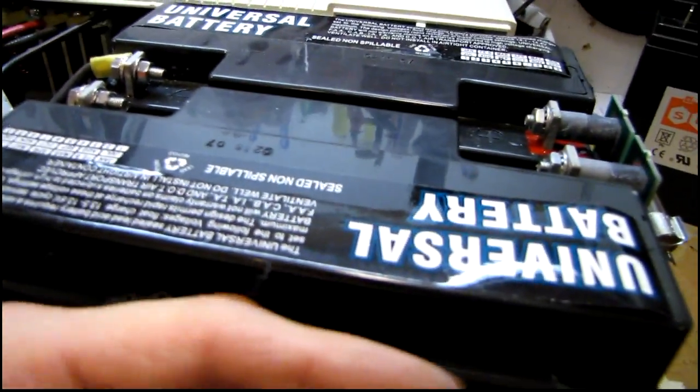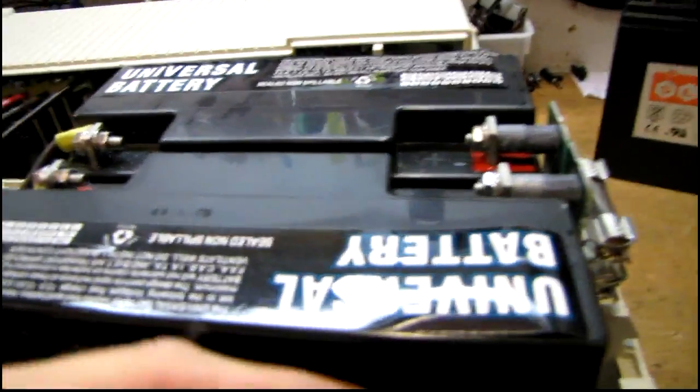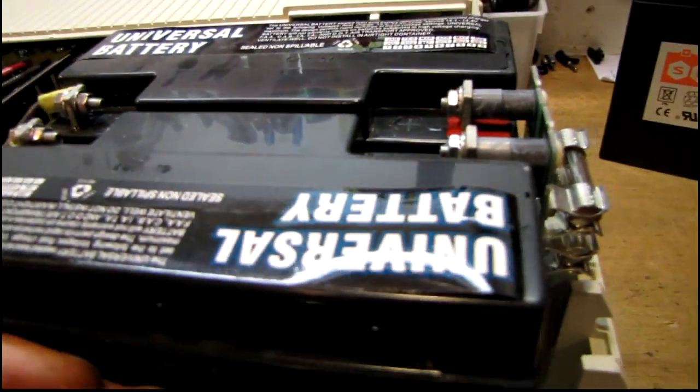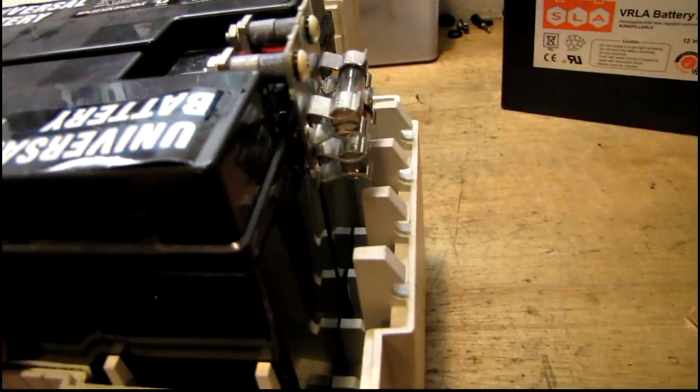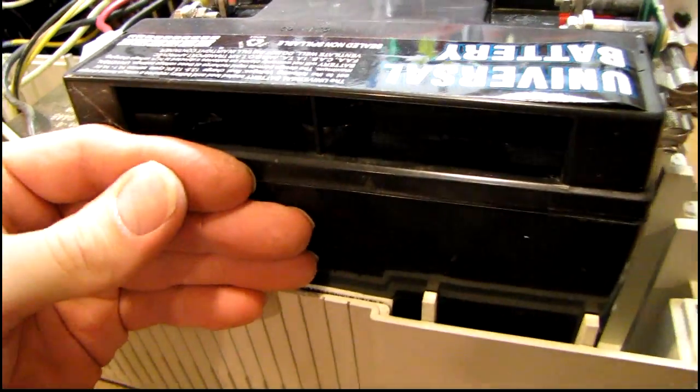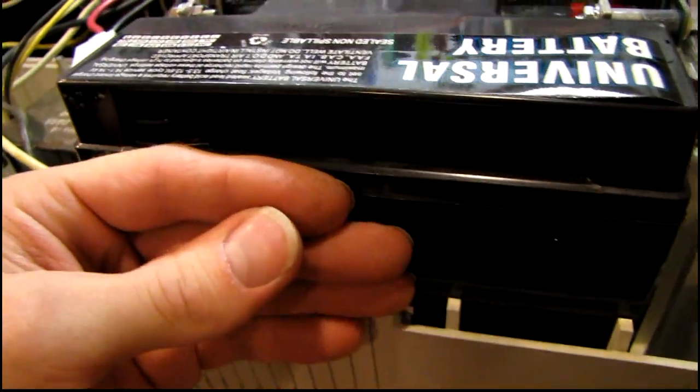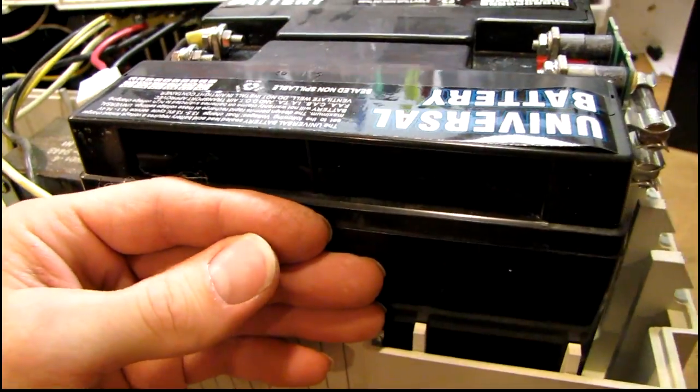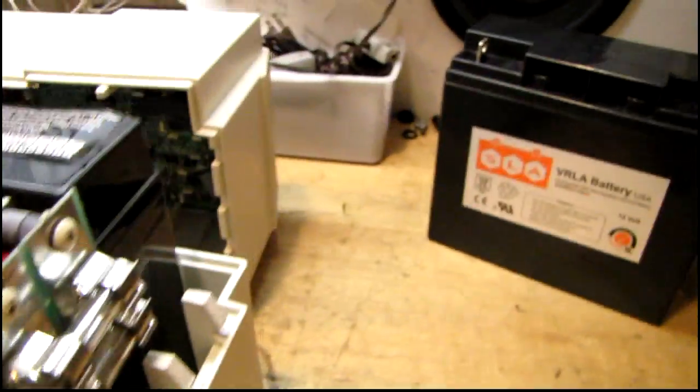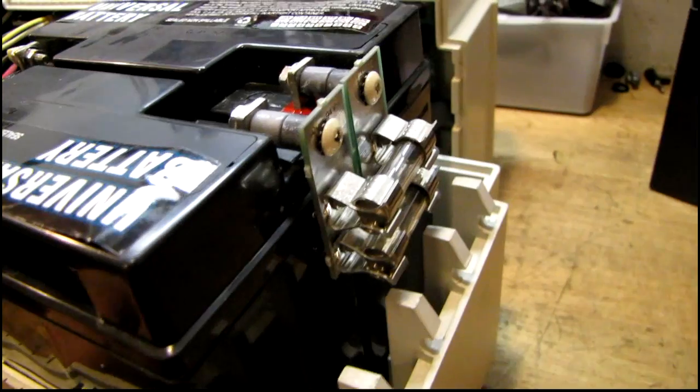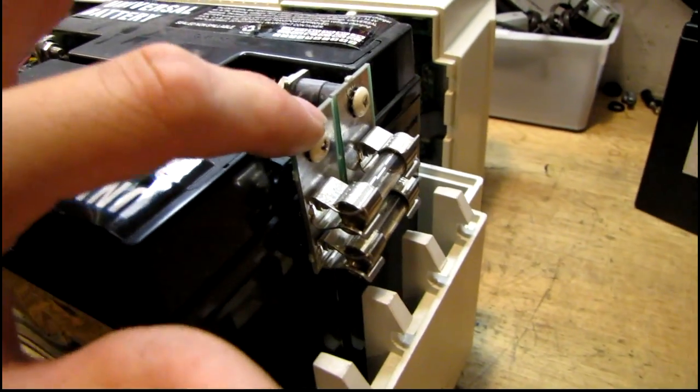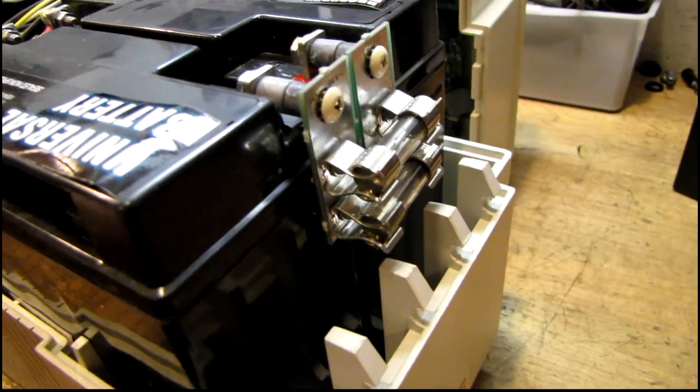Now these batteries are noticeably warm. They've probably been bad for quite a while. In fact, they're warmer here than they are here. So there's probably a couple of shorted cells in there.